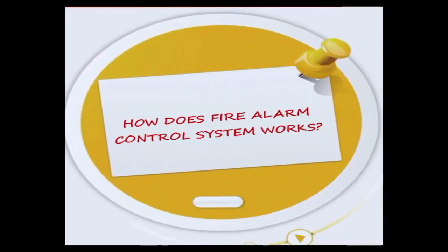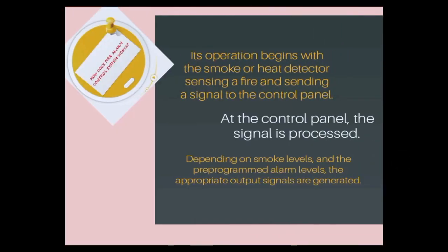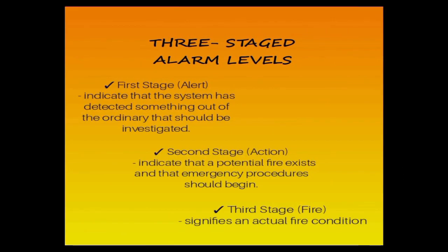So how does the fire alarm control system work? First, its operation begins with the smoke or heat detector sensing a fire and sending a signal to the control panel. At the control panel, the signal is processed. Depending on smoke levels and the pre-programmed alarm levels, the appropriate output signals are generated. So we have the 3-stage alarm levels. The first stage is alert, indicating that the system has detected something out of the ordinary that should be investigated. The second stage is action, indicating that a potential fire exists and that emergency procedures should begin. The third stage is fire, signifying an actual fire condition.